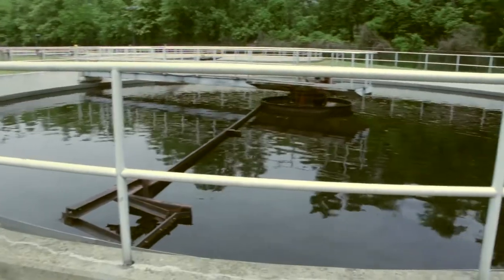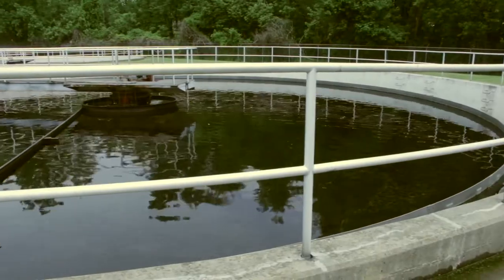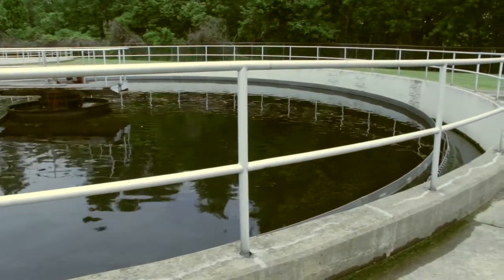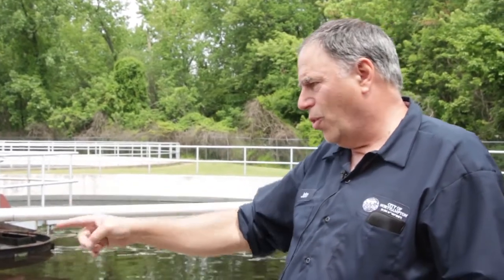Once the liquid goes through the aeration tanks, it comes out as a mixed liquor into our secondary clarifiers. That will sink to the bottom and form a secondary sludge, a WAS sludge. The water coming out under the baffles and over the sawtooth weirs will be the water going to the Connecticut River, with one more step of process before we let it out of the plant.